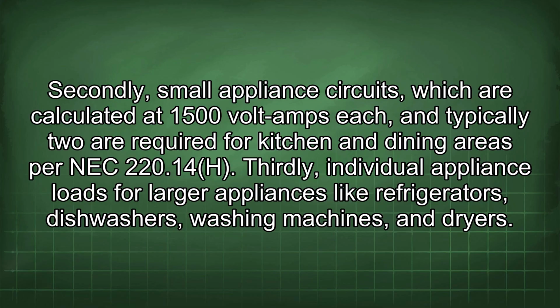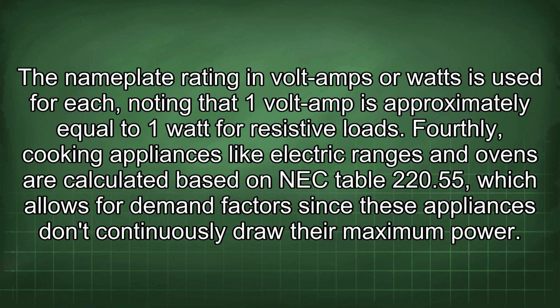220.14H. Thirdly, individual appliance loads for larger appliances like refrigerators, dishwashers, washing machines, and dryers. The nameplate rating in volt amps or watts is used for each, noting that 1 volt amp is approximately equal to 1 watt for resistive loads. Fourthly, cooking appliances like electric ranges and ovens are calculated based on NEC Table 220.55, which allows for demand factors since these appliances don't continuously draw their maximum power.